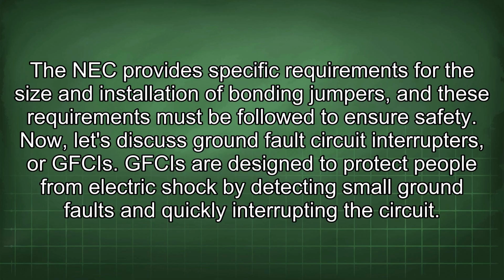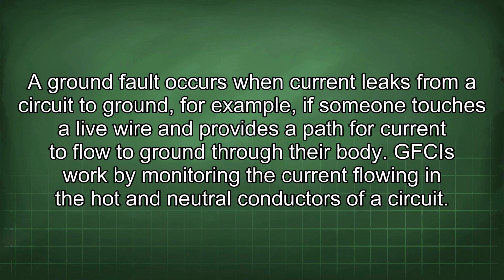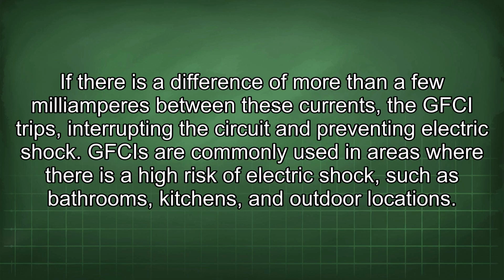Now let's discuss ground fault circuit interrupters, or GFCIs. GFCIs are designed to protect people from electric shock by detecting small ground faults and quickly interrupting the circuit. A ground fault occurs when current leaks from a circuit to ground. For example, if someone touches a live wire and provides a path for current to flow to ground through their body. GFCIs work by monitoring the current flowing in the hot and neutral conductors of a circuit. If there is a difference of more than a few milliamperes between these currents, the GFCI trips, interrupting the circuit and preventing electric shock. GFCIs are commonly used in areas where there is a high risk of electric shock, such as bathrooms, kitchens, and outdoor locations.